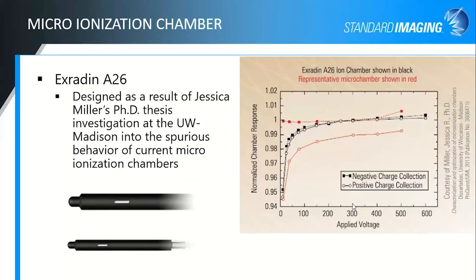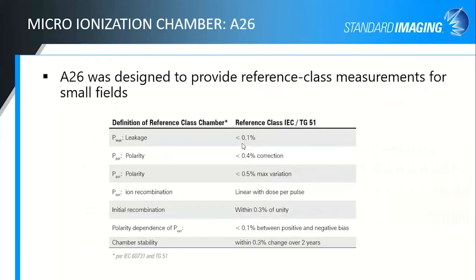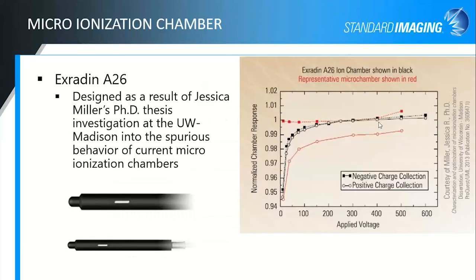The old standard, now working well, is the Exradin A26. This microchamber was designed as a result of Jessica Miller's Ph.D. thesis investigation at the UW-Madison. She was looking at all microchambers that were available on the market and why they were showing such inconsistent and illogical behavior when you looked at your polarity response. What she tracked it to was actually a conductance issue within the chamber that changed the electrical field and so would change the volume over which the chamber was actually collecting dose. And that was where this polarity issue came from.